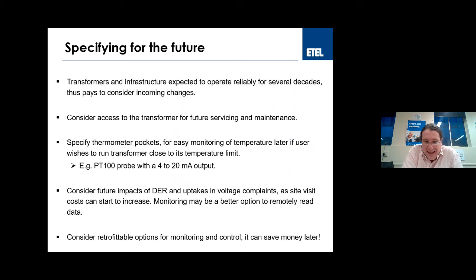Also, once DER and PV push the voltage high, eventually it reaches compliance limits and can no longer export, and customers start to complain to the utility. So it's worth the utility thinking about how to deal with a large number of voltage complaints, because it can reach a point where remote monitoring is a better option than sending people to site to gather data.